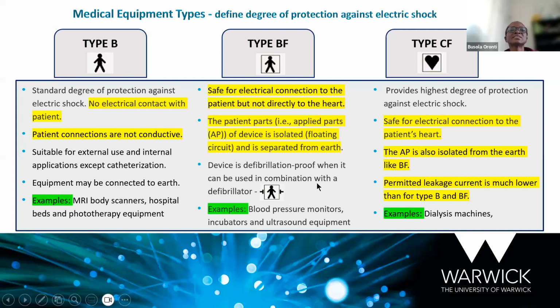And if a device can be used in combination with a defibrillator, then you will have this sign. You can compare the normal sign to this sign. And then thirdly, we have the third type of device, which offers the highest degree of protection, and it is safe to connect to the patient's heart. And the AP is also isolated from the earth, like we had in the case of the BF. So in this case, the permitted leakage current is much lower than either of the 2 types that we've considered. An example is a dialysis machine.